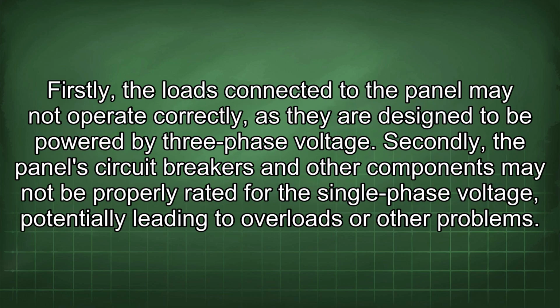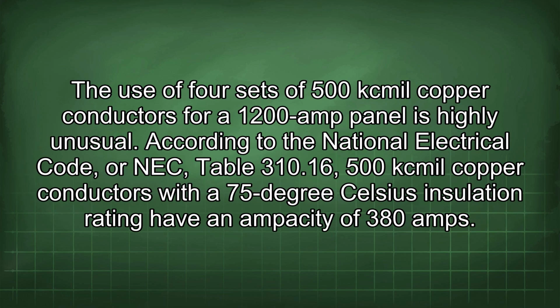Firstly, the loads connected to the panel may not operate correctly as they are designed to be powered by 3-phase voltage. Secondly, a panel's circuit breakers and other components may not be properly rated for the single-phase voltage, potentially leading to overloads or other problems. The use of 4 sets of 500 kcmil copper conductors for a 1200 amp panel is highly unusual. According to the National Electrical Code, or NEC, Table 310.16, 500 kcmil copper conductors with a 75°C insulation rating have an ampacity of 380 amps.